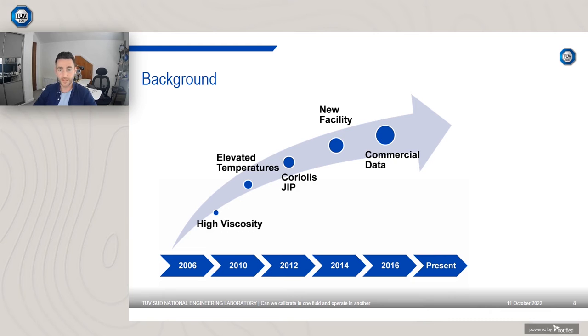So in terms of NEL's experience with the calibration of different fluids, I've been at NEL for 14 years, but going back 16 years, so back to 2006, 2 years before I started, NEL started to look at heavy oil, high viscosity fluids. They modified one of the facilities to operate up to 300 centipoise and looked at the effects of that on common flow meters. We've seen that there was a viscosity effect, and we actually created a JIP when I started in 2008. We launched a JIP into high viscosity fluids.